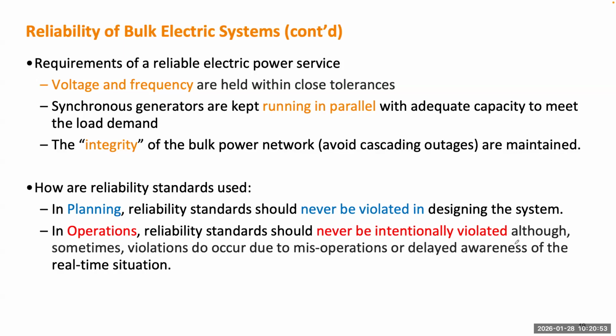On Monday, we talked about the definition of reliability for the bulk electric system, BES. There are three basic requirements for the bulk electric system to be stable. The first one, voltage and frequency should stay within their limits. And all the synchronous generators need to be synchronized, which means they will be running in parallel. And the third, the entire network needs to be an integrated network, so there should not be islanding or separation. Those are the three fundamental requirements for an electric power system.